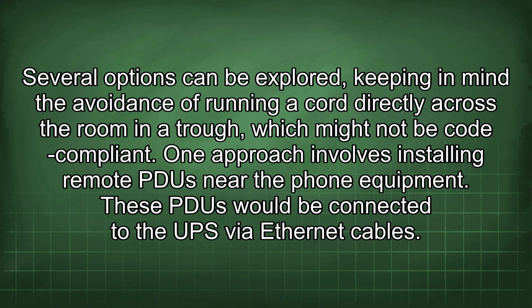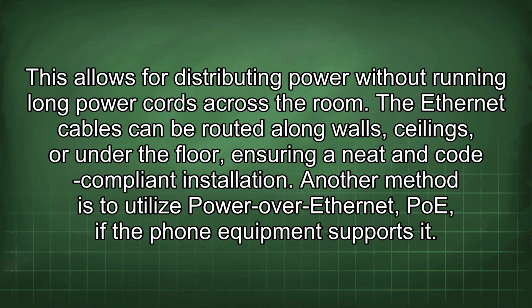One approach involves installing remote PDU near the phone equipment. These PDU would be connected to the UPS via Ethernet cables. This allows for distributing power without running long power cords across the room. The Ethernet cables can be routed along walls, ceilings, or under the floor, ensuring a neat and code-compliant installation.